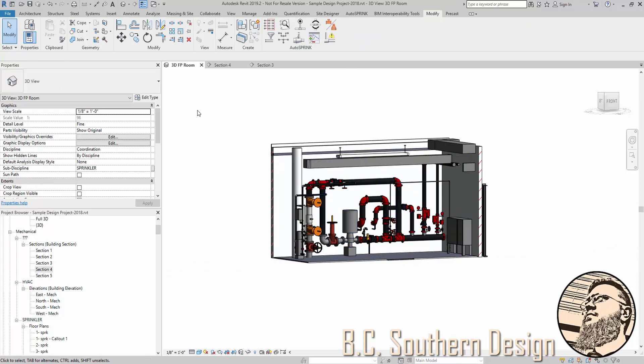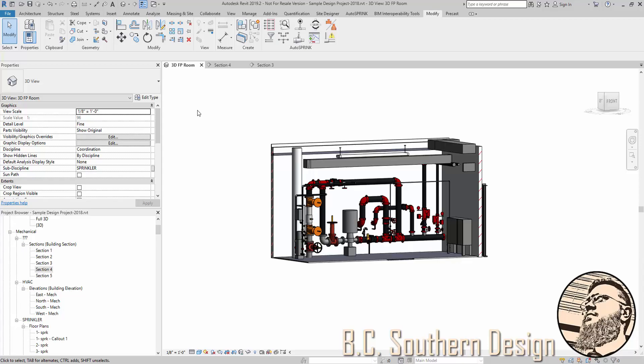So the process for this, if you create a riser or a pump room that you believe you can use in future projects, you create a group out of it, save it as a group to a different project, go in and do any cleanup work to it that you want. And then in the future, it's best to introduce it as a link because you'll find it's easier to move it around and align it and things like that, whereas groups can get a little messy sometimes. And once you have it in place, bind the link and ungroup it, and you're ready to go.